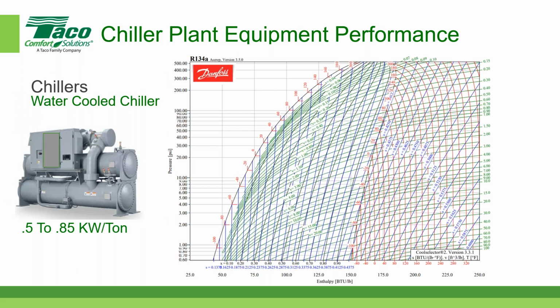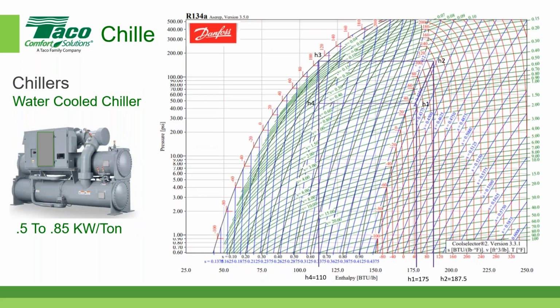I'm not going to spend any time going through the details. I just have it mapped out here. This is our H1 value right here. That's entering the compressor. That's 175 BTUs per pound. Here's the enthalpy leaving the compressor. Here's the enthalpy entering the evaporator, and the enthalpy leaving the evaporator is the same as the enthalpy entering the compressor. And these numbers will help us understand how much energy this chiller is going to consume.